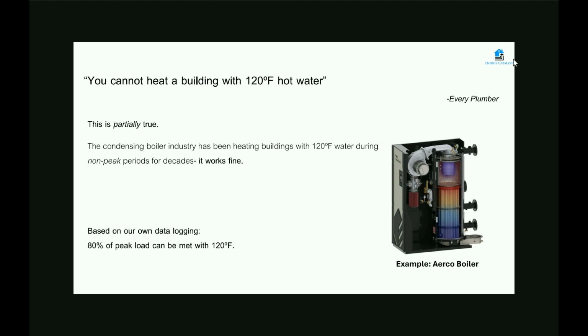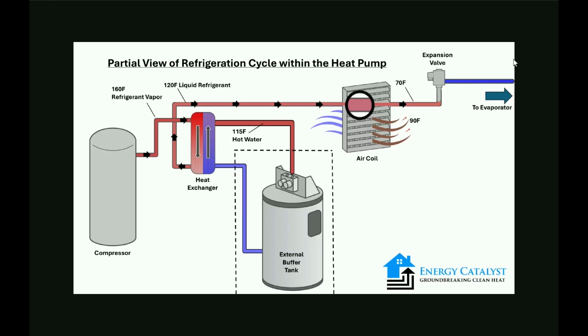But as we all know, a condensing boiler, if it needs to, on a peak day, can just make higher temperature hot water. So it has that ability to bridge the gap if it has to, right? And heat pumps typically don't have that ability. They can't go up to 180 on the coldest day of the year. And so we need to find a way to bridge that gap. Now, based on our own data logging, what we find is that most buildings can cover about 80% of their peak load with 120 degree hot water. So there's only a 20% heating gap that has to be filled.